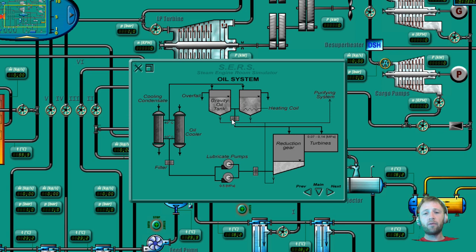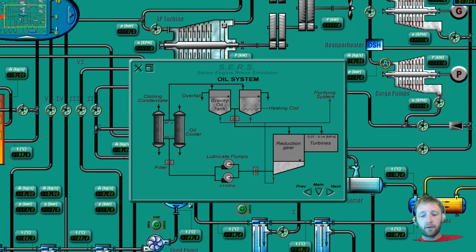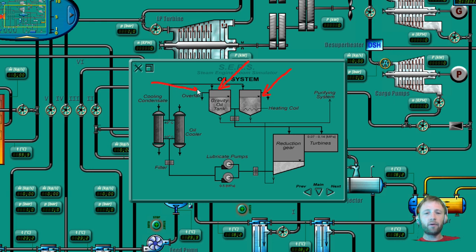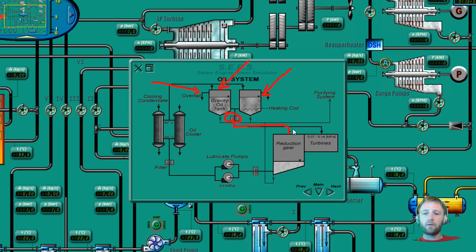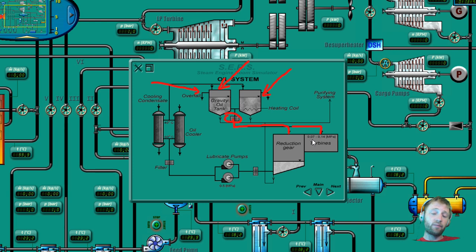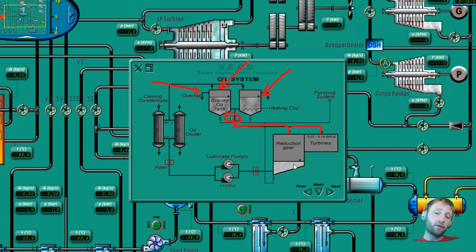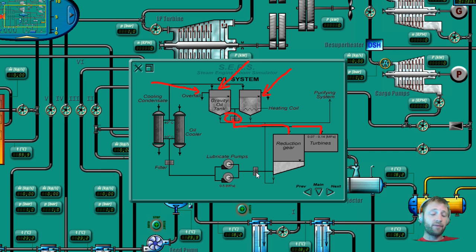The thing that we need to prevent from damaging our turbine pumps is that there is always supply of lubricating oil. From the gravity tanks, the oil passing some filters here, and I will use my pen here to show. This is our gravity tanks which contain the oil. We have also an overflow here, filter and some filters in this position. After that, the oil travels here, lubricates the reduction gear and also our turbines. Our turbines are lubricated with pressure from 0.37 MPa to 0.14 MPa.